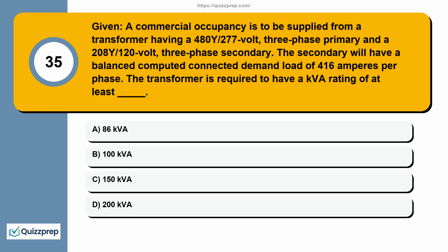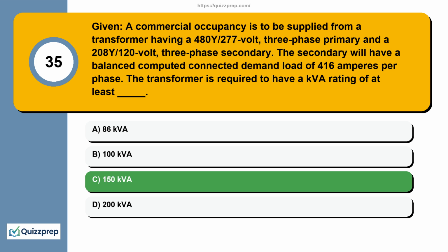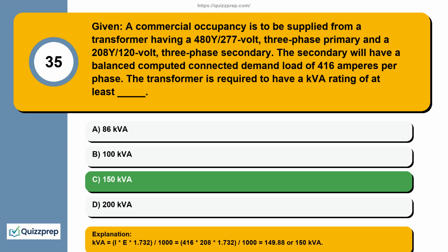Question 35. Given, a commercial occupancy is to be supplied from a transformer having a 480Y/277 volt, 3-phase primary and a 208Y/120 volt, 3-phase secondary. The secondary will have a balanced computed connected demand load of 416 amperes per phase. The transformer is required to have a kVA rating of at least 86 kVA, 100 kVA, 150 kVA, 200 kVA. kVA equals I*E*1.732/1000 equals 416*208*1.732/1000 equals 149.88, or 150 kVA.